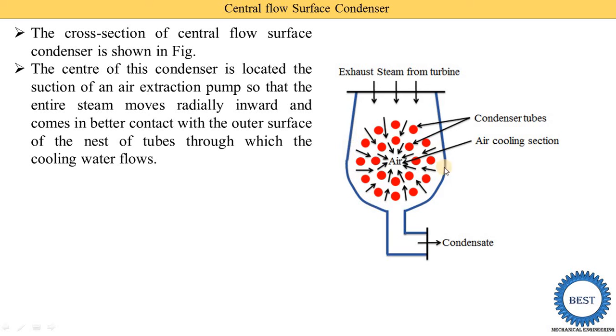Why radially? Because this is a circular cross-section — in a circle, the steam moves radially inwards. As you can see, the arrows indicate radially inward movement. The steam comes into better contact with the outer surface of the nest of tubes — that is, the number of tubes through which cooling water flows. Steam flows from the outside, and because it moves radially inward, it comes into better contact with the tubes and proper cooling is carried out.